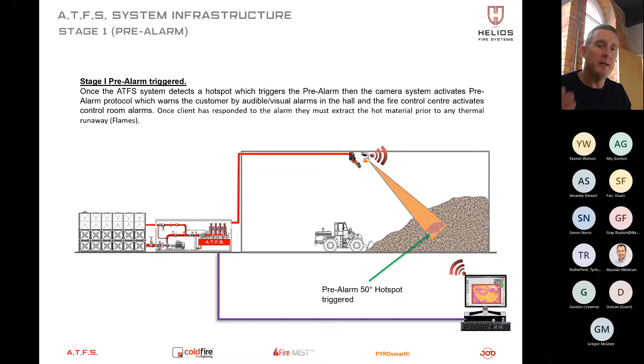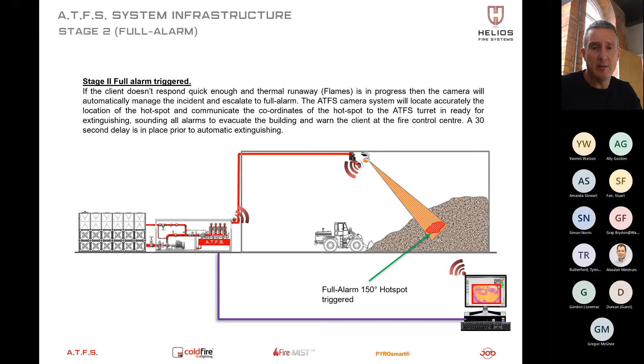So we have to give a 30-second evacuation time for the site, so to get plant and machinery out of the building, and more importantly get operatives and all the employees that are working in that area out of the building before we activate the cannon system. What we don't want to be doing is activating the cannon on a person that's walking through the fire exit. So in this case, we detect it, we send the signal to the camera system and cannon. The cannon system then activates the alarms, and 30 seconds later, we are then activating the targeted suppression.